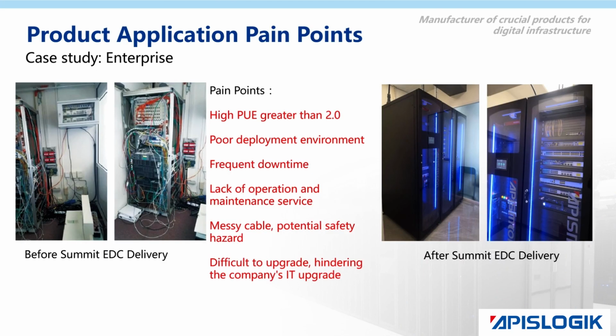This is a case study of an enterprise micro data center consisting of 3 units, with a total capacity of 20 kilowatts and a provision of 74 U of IT equipment space. Ample capacity has been reserved to accommodate future upgrades and updates of IT equipment. The previous data center environment was extremely harsh, making it impossible to upgrade and update equipment effectively. The cooling system comprised of 2 3P air conditioners proved inadequate, leading to frequent system failures during summer, disrupting normal company operations. After the upgrade, the comprehensive power usage effectiveness (PUE) has been reduced to 1.25 or below throughout the year. Additionally, the stability of the equipment has significantly improved, and it is expected to extend the lifespan of the IT equipment. Furthermore, the company's IT engineers have upgraded the existing company operations software, facilitating efficient enterprise management.